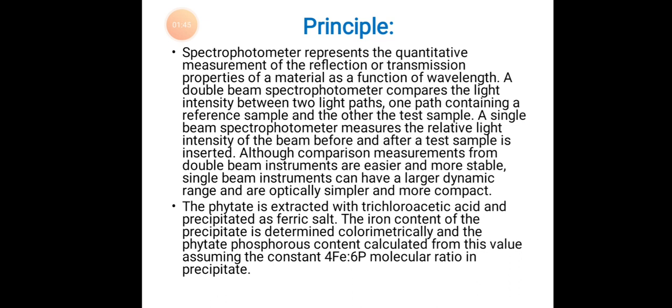A single beam spectrophotometer measures the relative light intensity of beam before and after a sample is inserted. Although comparison measurements from double beam instruments are easier and more stable, single beam instruments can have a larger dynamic range and are optically simpler and more compact.